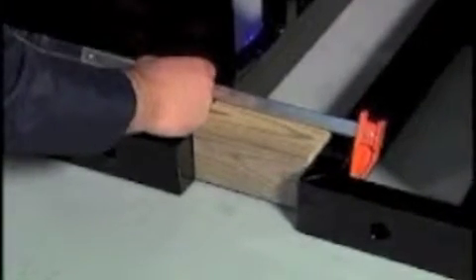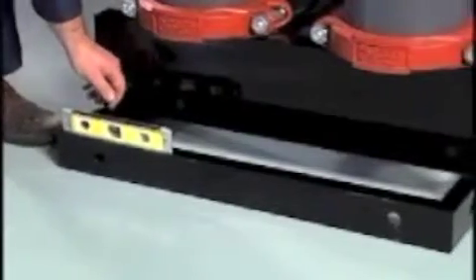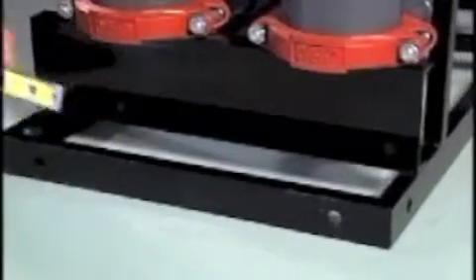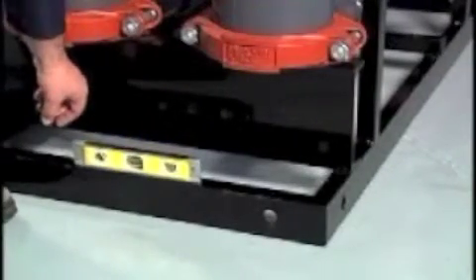Use large C-clamps where UF rack unit A and UF rack unit B are joined, and also where UF rack unit B and the CIP unit are spaced apart by the width of the wood spacers. Start the leveling process at the highest corner by running a bubble level completely around the C-channel frame perimeter of the UF machine and CIP.